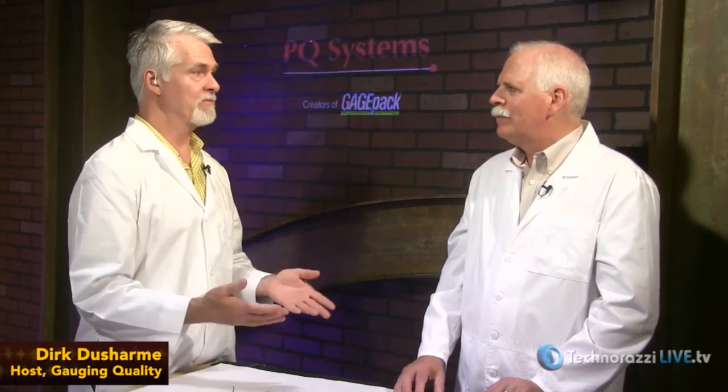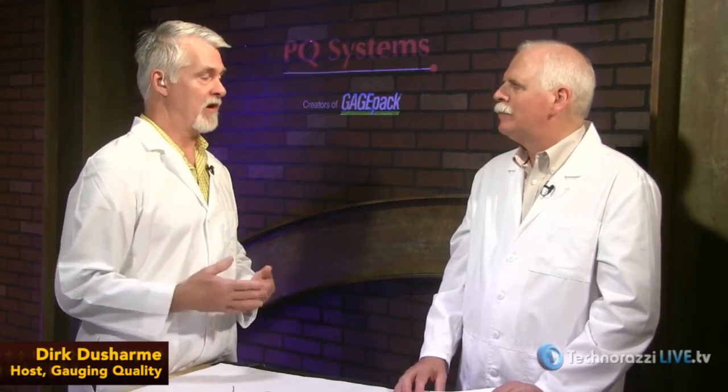Yeah. So if an auditor comes in and wants to know, hey, how can you use this outside the range of the instrument, he can show them documentation and basically show how he has validated what he's doing. Right, so the documentation is part of the step, making sure his quality processes allow him to work in non-standard forms. Make sure everyone in his company is on board with it. Very important would be the customer that's buying the product. Are they aware of this? That here's what we're doing, here's our results. If everybody is signed on, I would say his process is valid. He was very complete in his data and in his methodology. Okay, so that seemed like a great response from him.